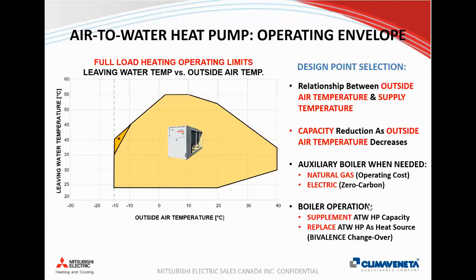So again, just looking at the operating envelope and design point selection, we know that we will have a relationship between outside air temperature and the supply temperature from the heat pump. In addition to this, it's not shown in the diagram, but we'll talk about it in the next slides, we'll have a capacity reduction as the outside air temperature decreases.